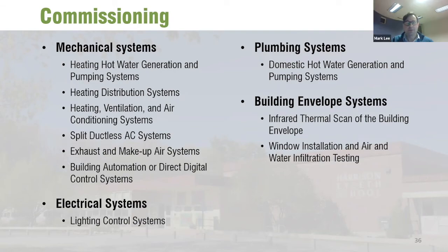Sometimes what they'll do is look at the controls. Most new systems have programmed controls for the equipment, so the programmer of the control system changes the parameters around the operation of the units as the commissioning agent goes through startup. That controls programming gets modified as they go through the checklist, with the controls contractor beside them. It's approached as a team, with the contractor, the commissioning agent, and the controls contractor working together as they get ready to start up the equipment.